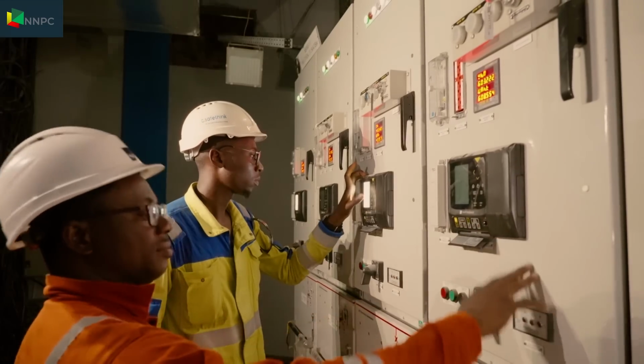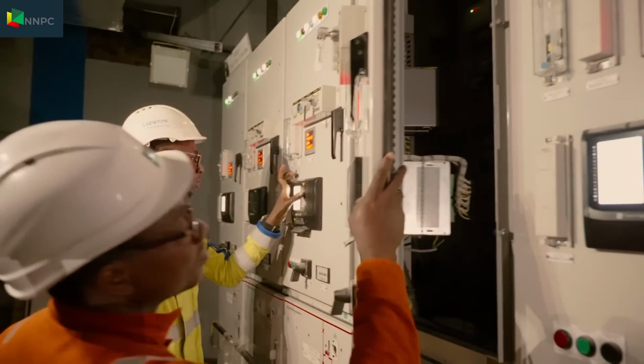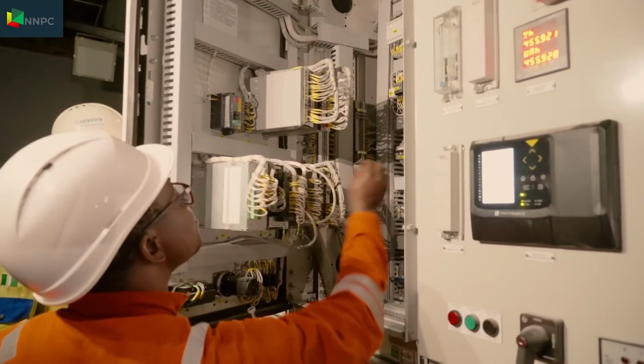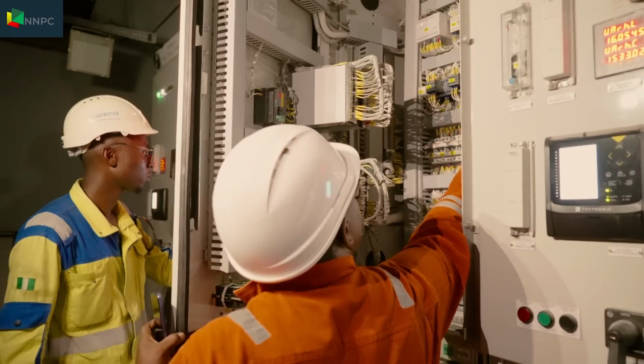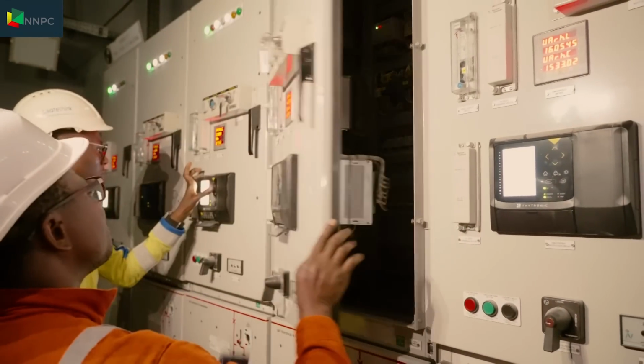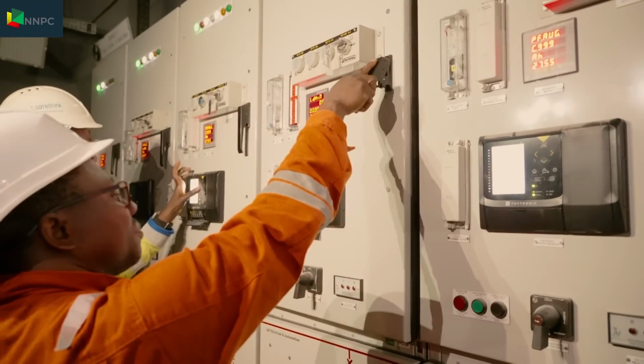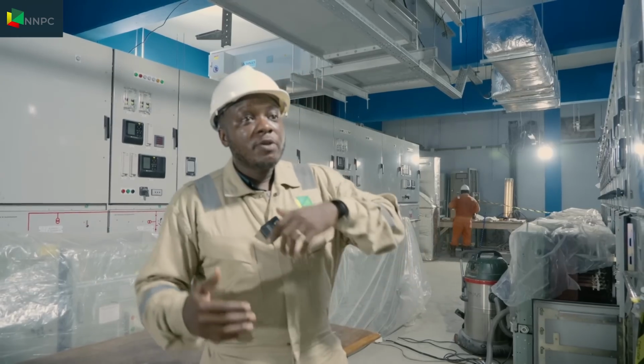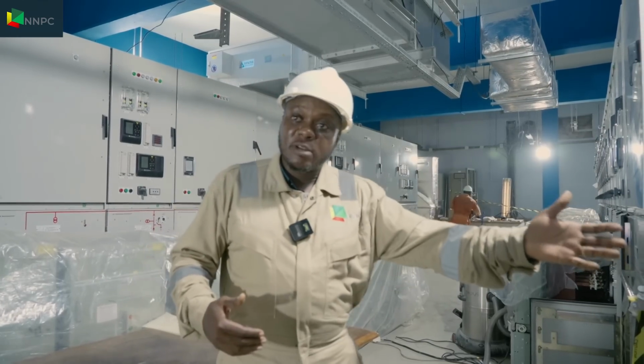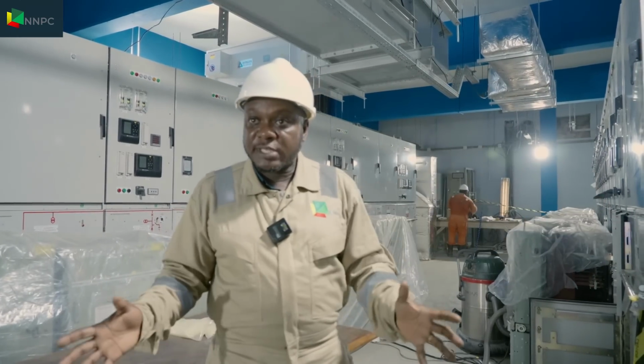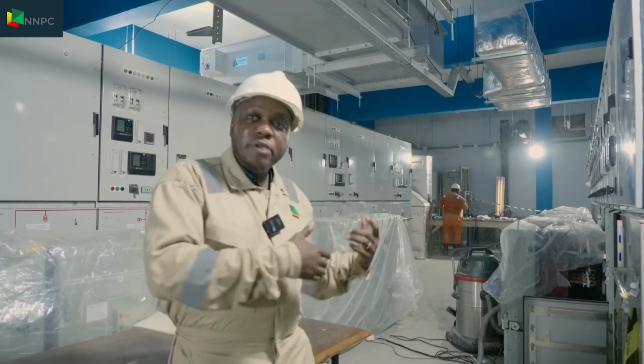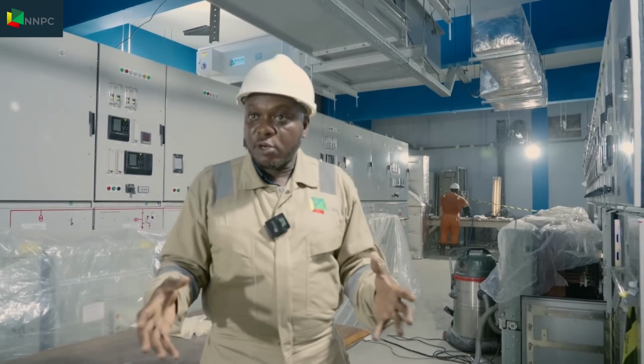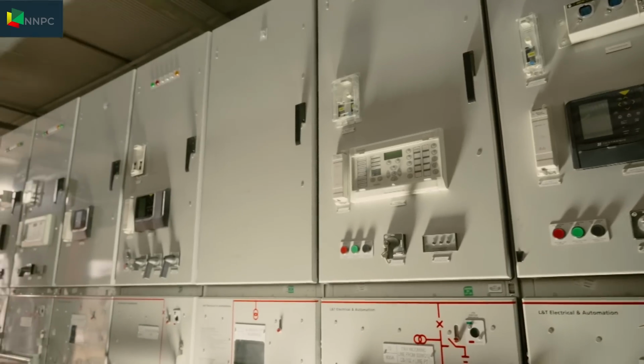It's designed in such a way that the new and the old refinery, we call it old, although everything there has been replaced and it should change the name from old to new now, it supplies Refinery 1 and Refinery 2 power. So from here, you can send power to Refinery 1. Even if there's an issue there, this place stays up. In Refinery 2, even if there's an issue there, this place stays up. So here, no matter what, has to be up.